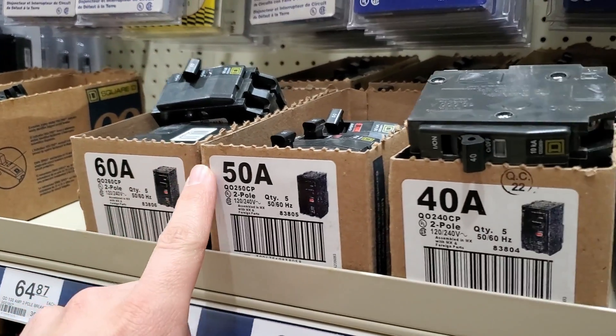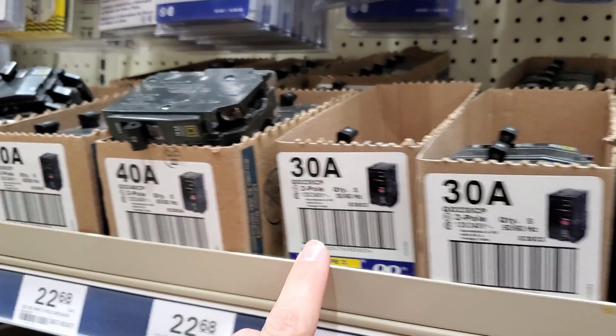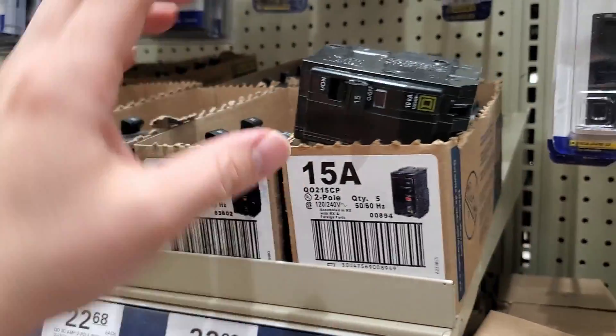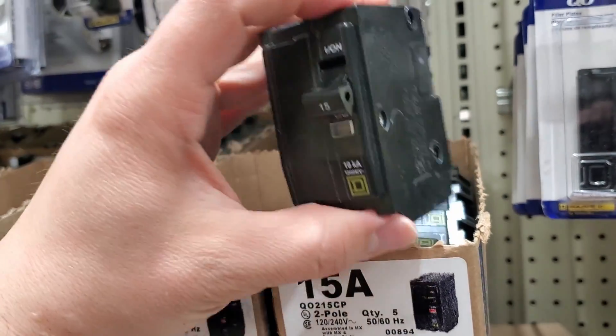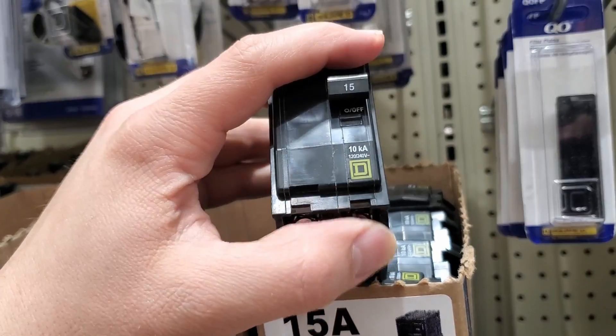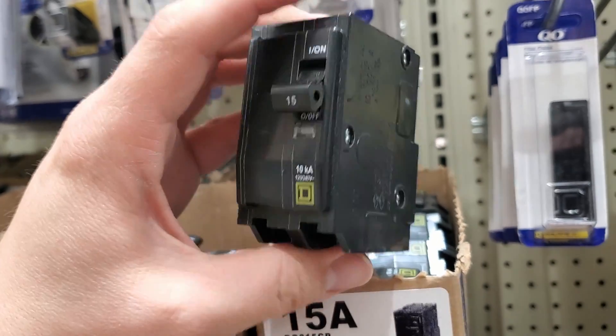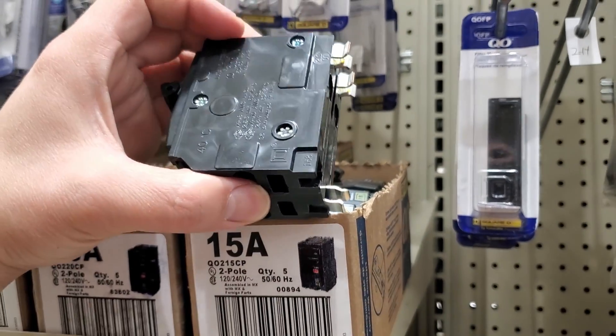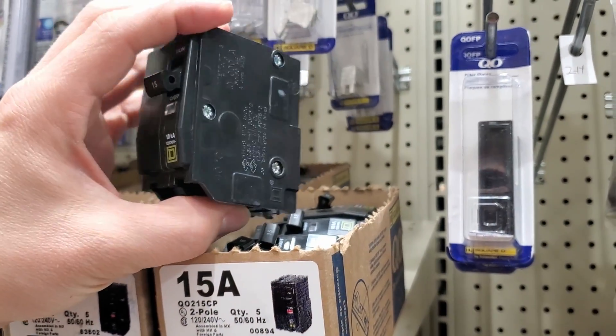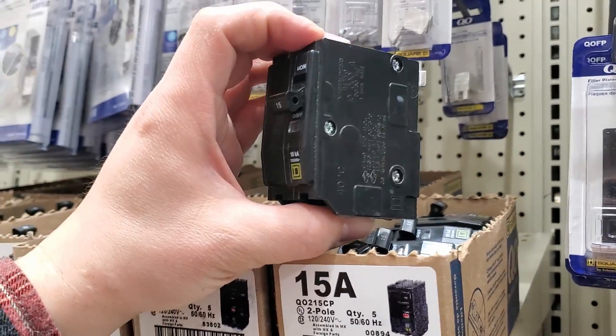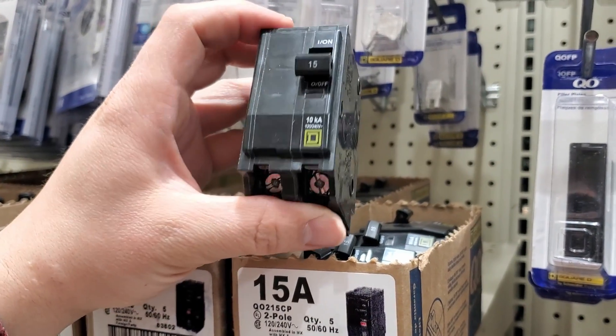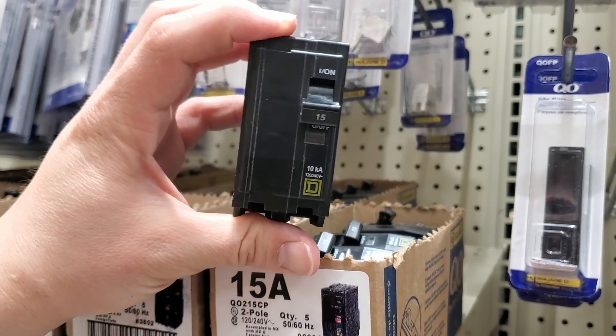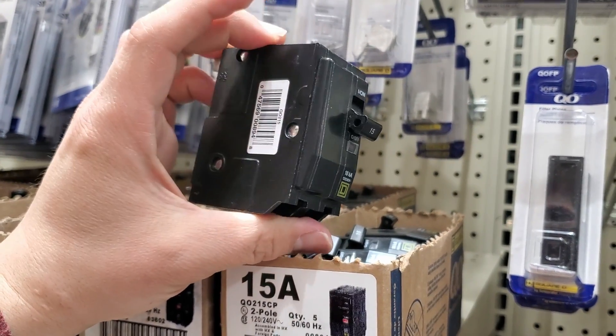When you're choosing your double pole breaker to feed the sense energy monitor, you want to choose the smallest available size. In this case it's going to be 15 amp, typically the smallest double pole breaker you'll be able to get. The sense energy monitor uses a ridiculously small amount of power, so it wouldn't even need anywhere near 15 amps. And the device itself is certified to be connected to any size double pole breaker, but it just makes sense to use the smallest available breaker.